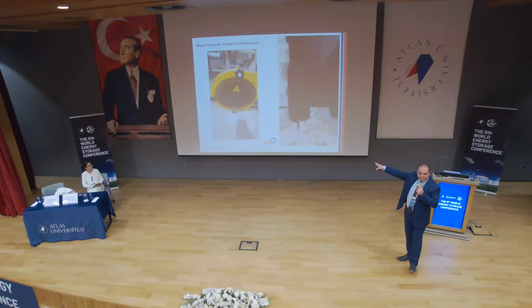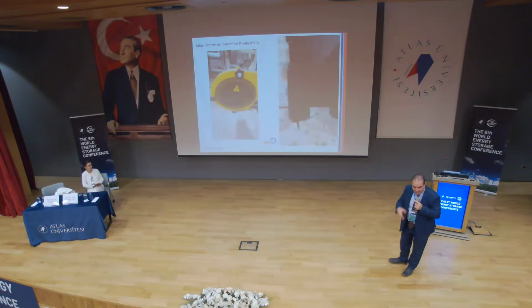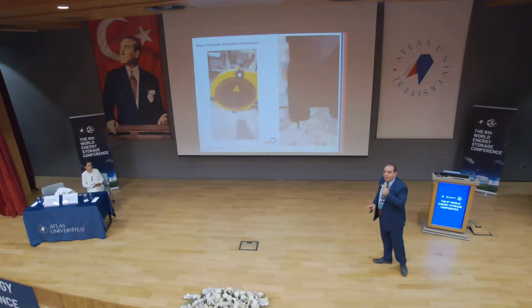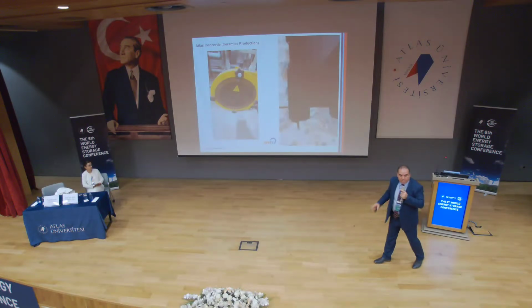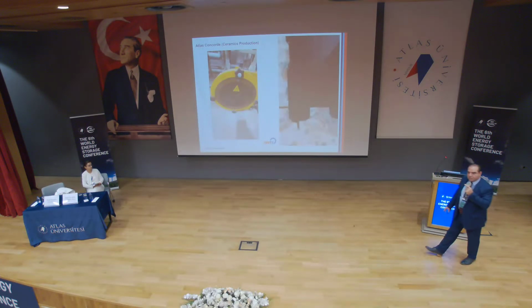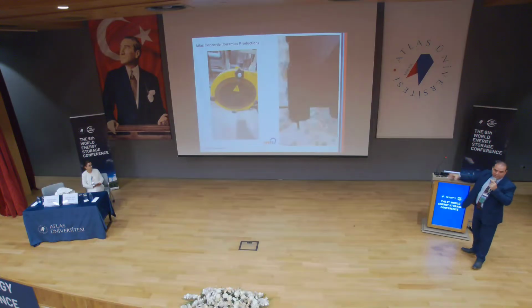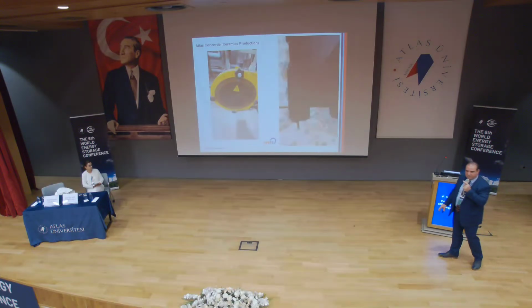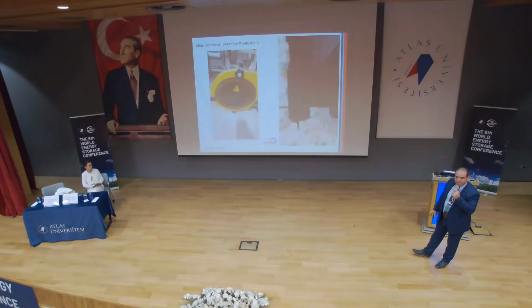We are now condensing. Many companies have low-grade heat, but they ask, if we recover it, what do we do with it? Having water at 40 or 50 degrees isn't really useful to us. That's where energy storage and heat upgrades come in. So the follow-on project from iWays is called StreamStep, where we take the low-grade energy and elevate the temperature to 150 and 200 degrees in two areas using high-temperature heat pumps.